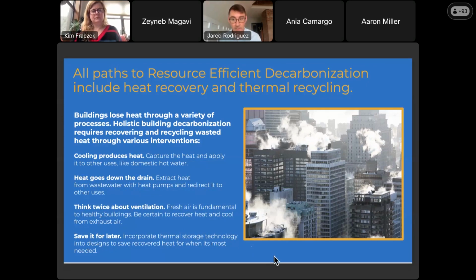Cooling produces heat, right? Folks often forget about that. There are cooling towers that run in New York City year-round, especially where there are high internal loads or glass buildings with very high solar heat gain on the south side. Those cooling towers are running, rejecting heat, while at the same time burning gas to heat the north side of the building. This is generally unacceptable—we have to be capturing this heat and getting it back into the building.